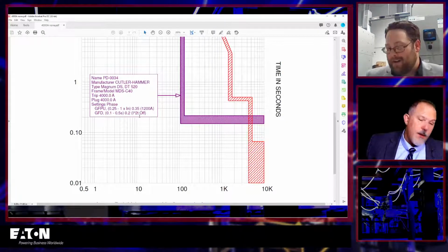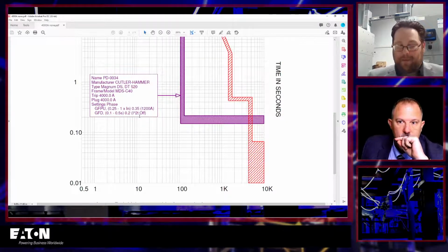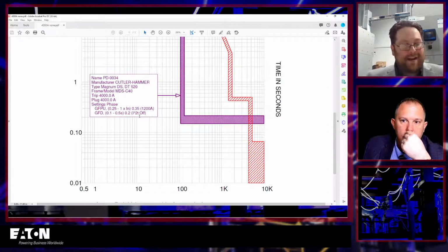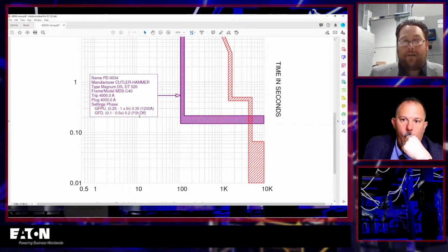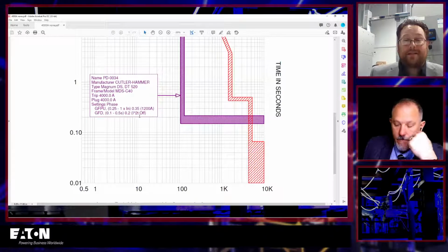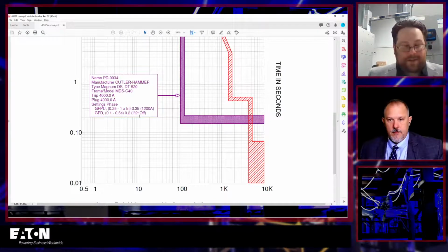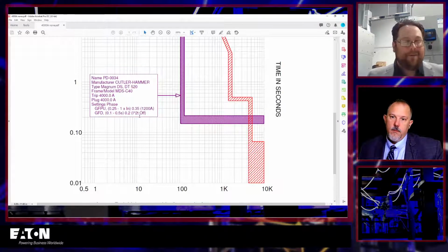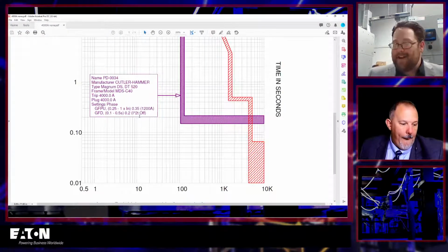I think earlier, Tom, and this is probably a good point to bring it up, I was talking to you about the presentation tonight, and you brought up that it's not uncommon to have only one level of ground fault in a system, and how dangerous that can be. My story is that years ago, when I was in the role doing arc flash studies and coordination studies, I'll never forget getting a phone call from a very upset customer. The consultant engineer was on the phone, and the contractor, and all these people. Ultimately, I had determined their settings, so when the breaker tripped, it was obviously my fault.